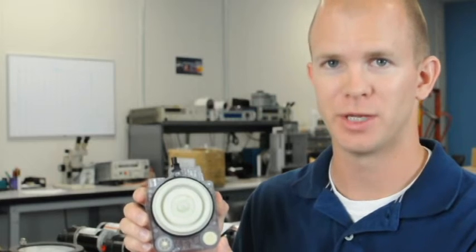Now that we've removed the upper and lower end caps, we can now remove the diaphragms and the check valves. Before you remove the check valves, make sure to note the orientation so that when you install the new check valves they're facing in the same direction.